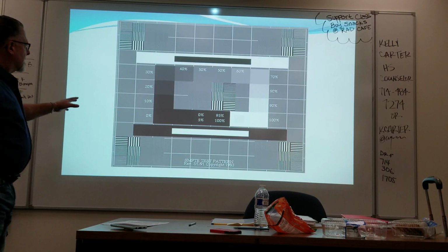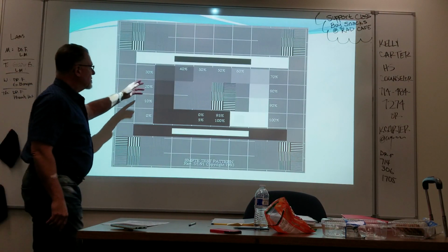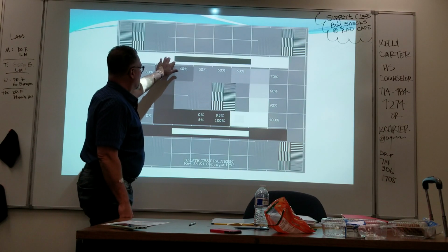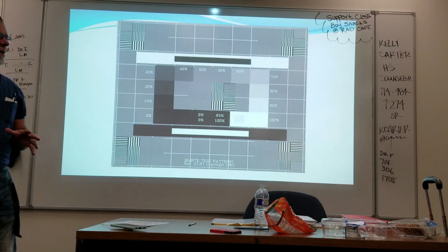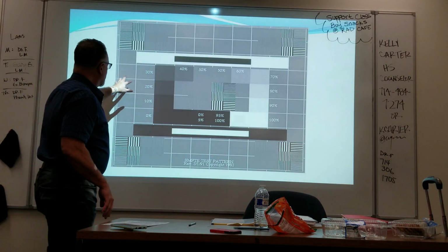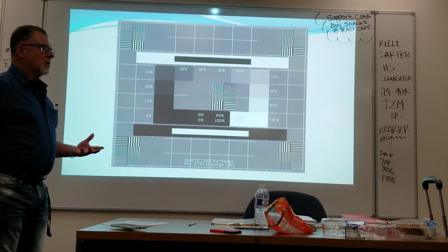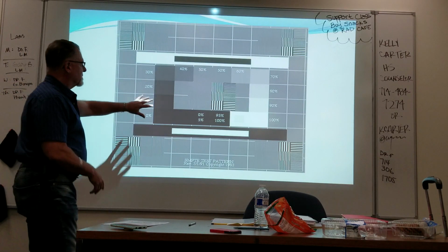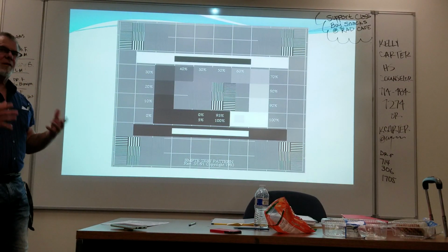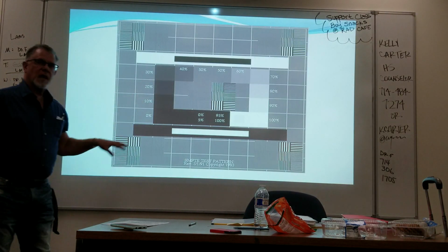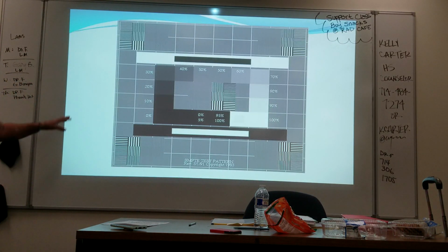displays are judged. So when you're looking at this on your display, there's a couple of things. You should look at the transition between white and black and white. It should be clear and crisp. It shouldn't be smudged. The squares should actually look like squares. On a typical II type system, this is where you would see your pin cushion distortion perhaps, if you're using a phantom that you're actually imaging. Generally, these reside in the computer, so you're only looking at the display. Okay? And this should look like a square.